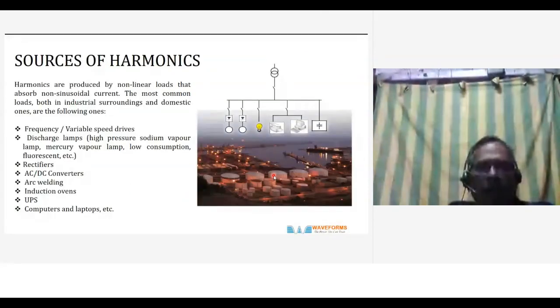So these are different sources of harmonics. Anything which is AC to DC or DC to AC conversion. When you say AC to DC, that is a converter, and DC to AC is an inverter. So UPS, welding machines, induction furnaces, computers, a lot of all this generate these harmonics. And now all loads are like this; there's no load without these types of loads.